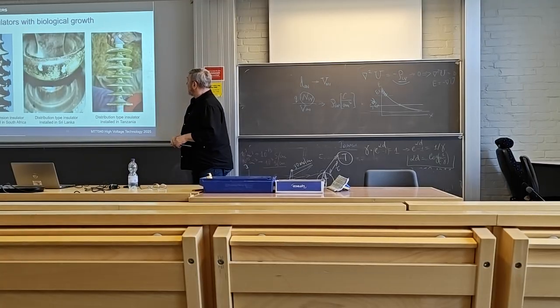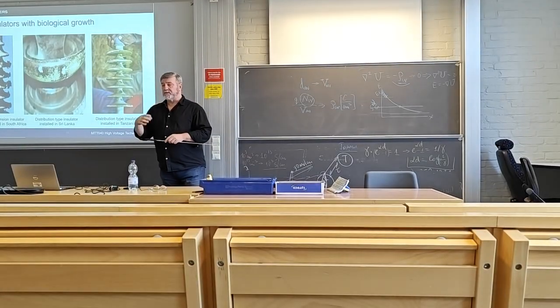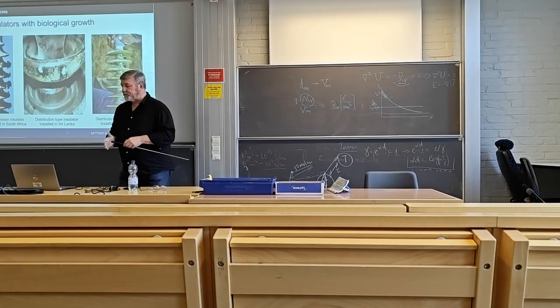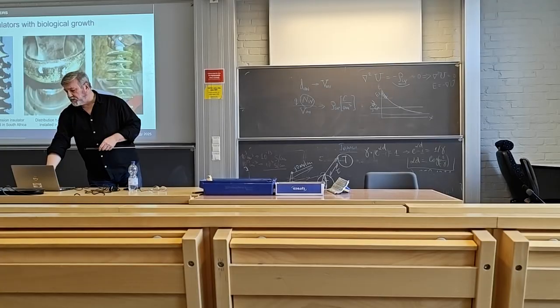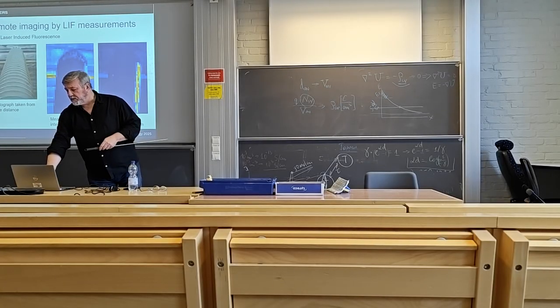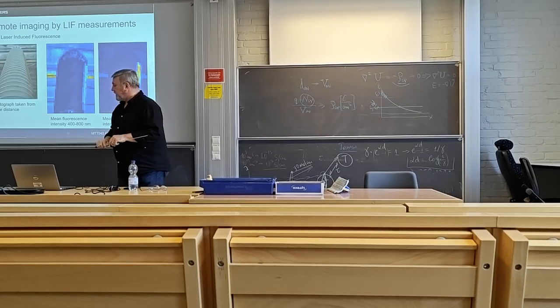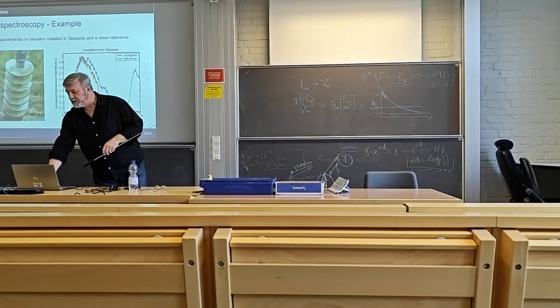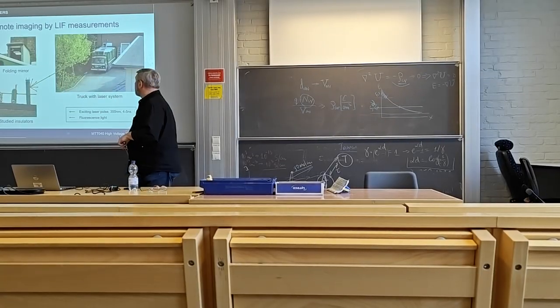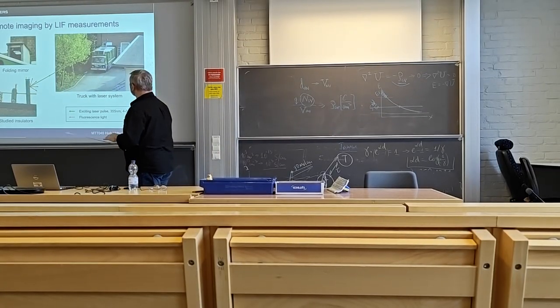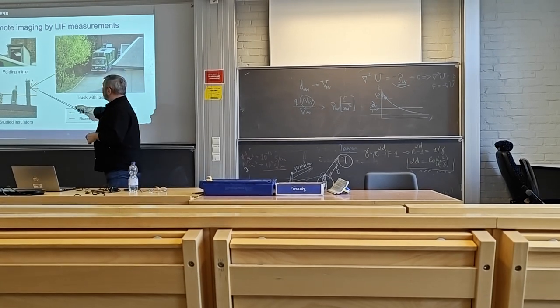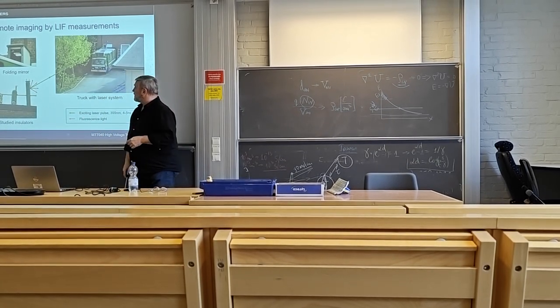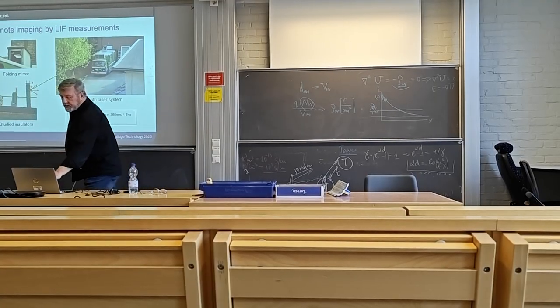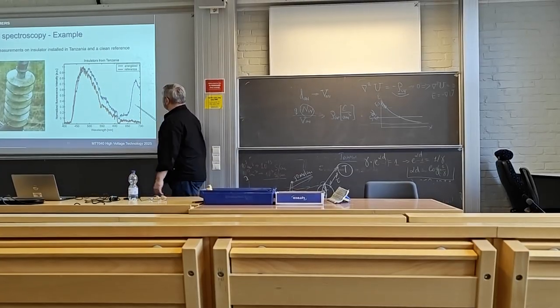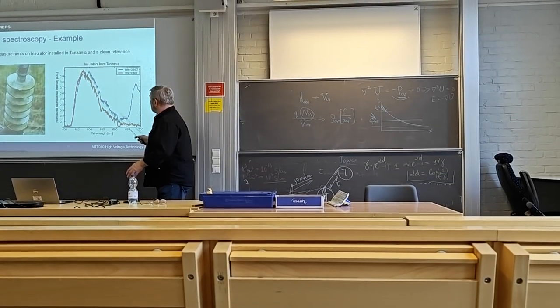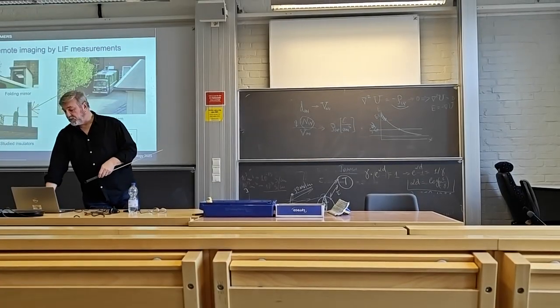Again, it's all about wetting - if it comes to wetting, it creates conductive paths, and then it's trouble. There is a technique we developed some time ago where one may use fluorescence measurements to evaluate the performance of the contamination level. You have a truck like that, you send a laser beam, collect the reflected light, put this in the spectrum like that, and then decide what the contamination is, what the level is, and so on. So there are techniques for doing these things.